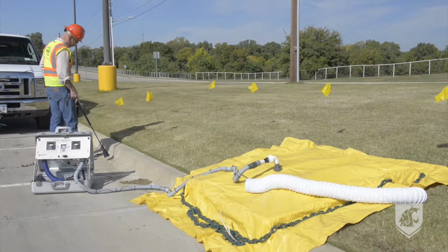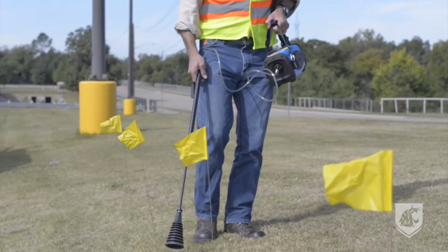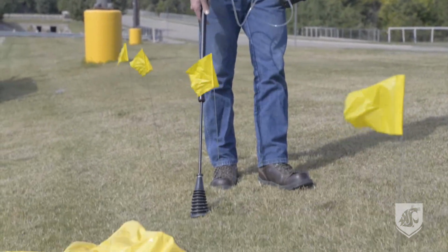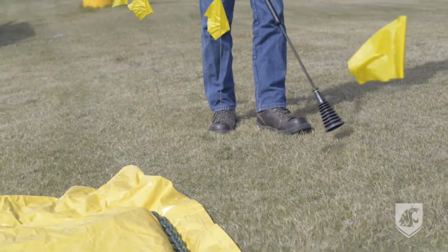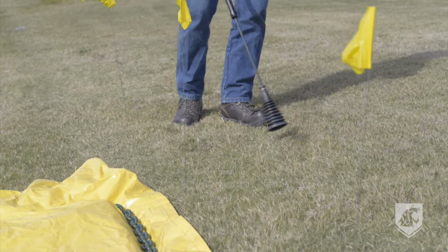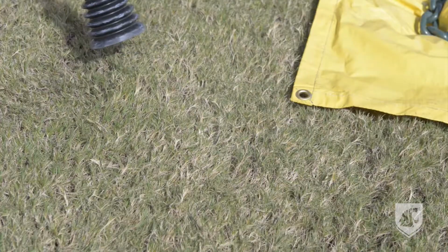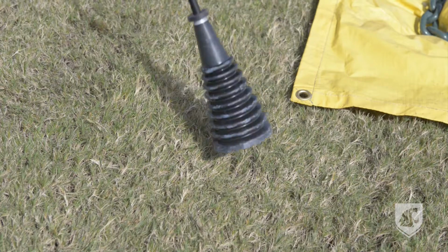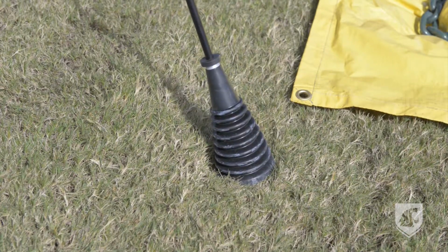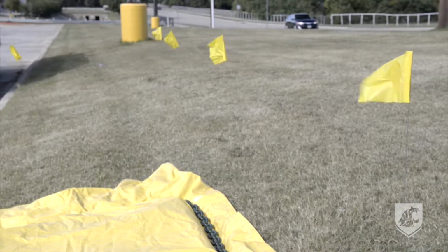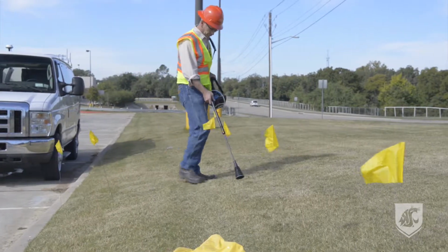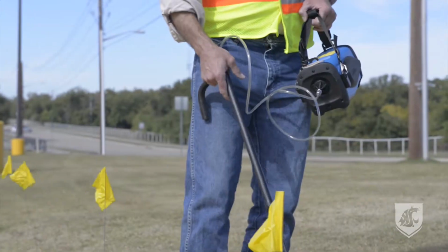So we've identified a leak. Then we can scan with surface scanning equipment to pick up the center line of where the leak is. He's using an infrared methane instrument right now to locate the extent of the leak. We use the survey flags to mark the number of points that we think we need to sample to cover this entire leak.